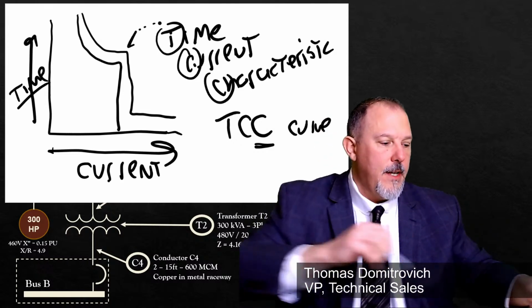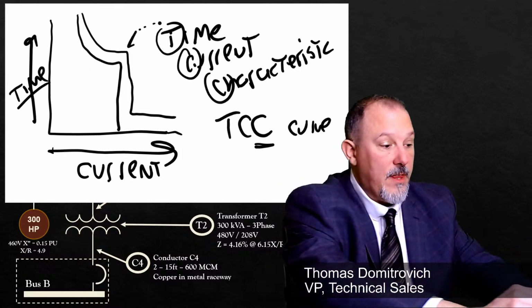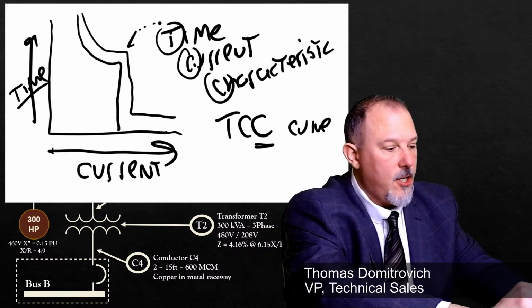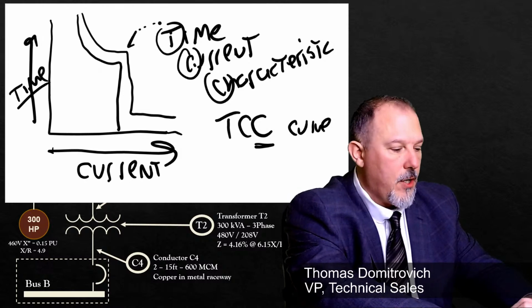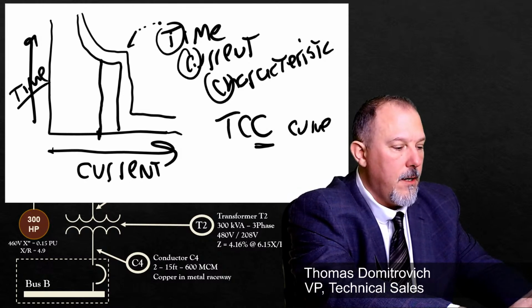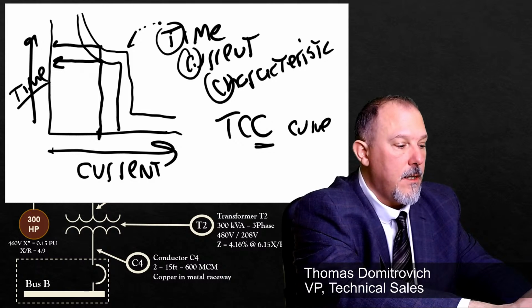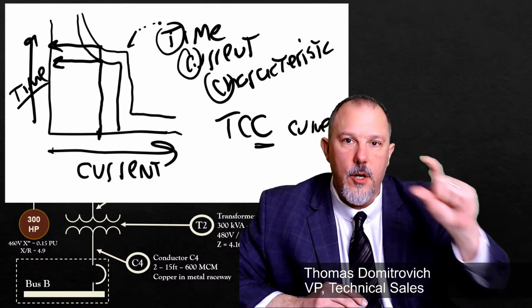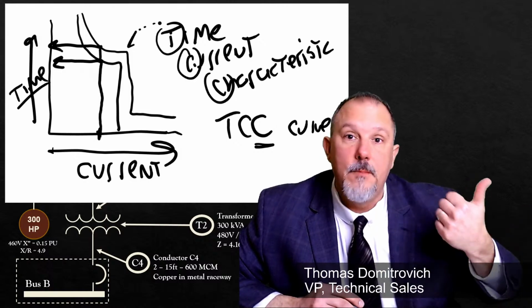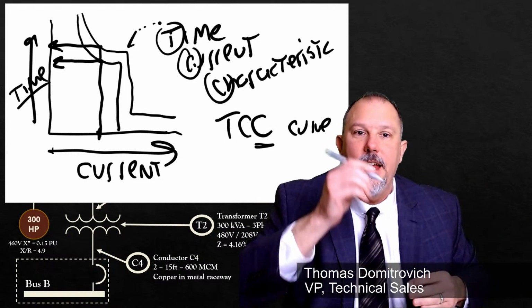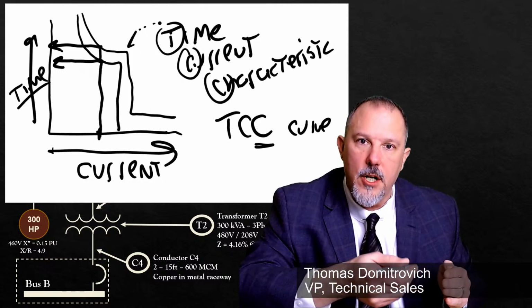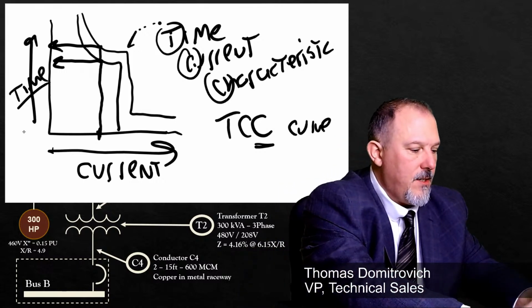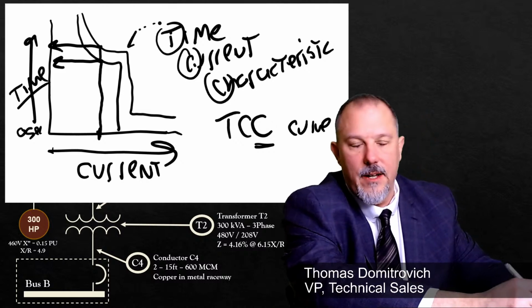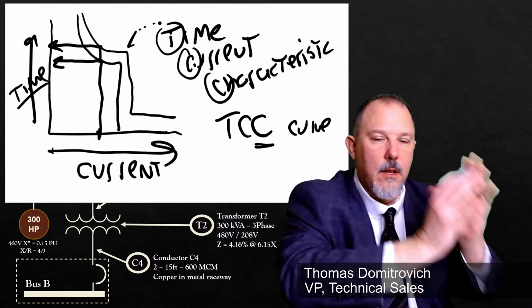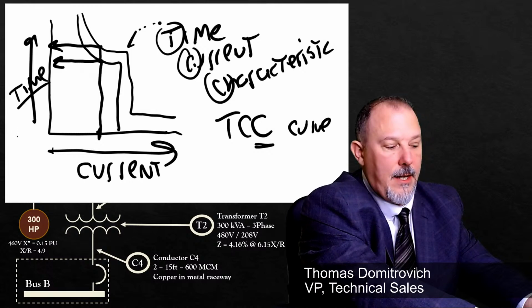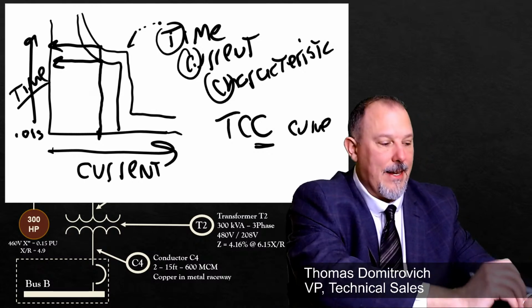Time current characteristic curve. Now, what this TCC curve tells me is, for any value of current, so let's say I have a value of current here, I know that this device will trip somewhere in between those two times. Those could be seconds, that could be minutes, depending upon the value of current. And what we know is, the higher the current, the shorter the time. If this is 0 seconds, or actually it's not typically 0 seconds, and we're going to look at the time current characteristic curve, this is typically 0.01 seconds, okay?